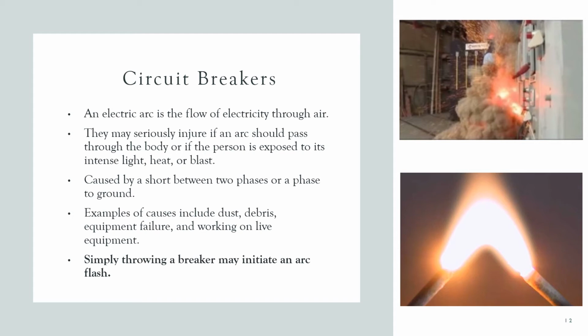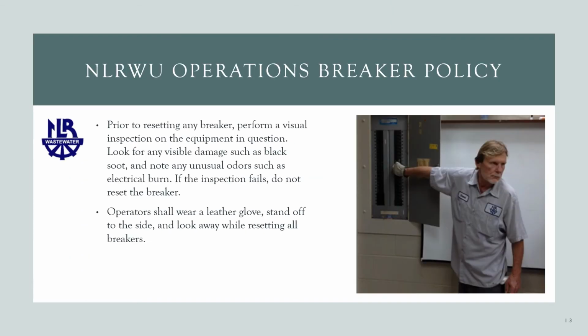They're caused by shorts between two phases or a phase to ground, and some examples of what can cause them include dust, debris, equipment failure, and working on live equipment. Sometimes all it takes to generate an arc is to throw a breaker. Prior to resetting any breaker, perform a visual inspection on the equipment in question. Look for any visible damage such as black soot and note any unusual odor such as electrical burn. If the inspection fails, do not reset the breaker.